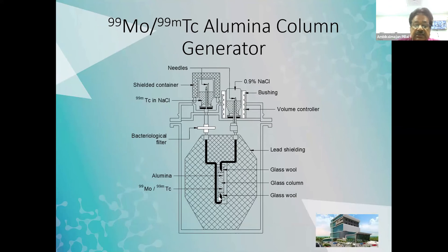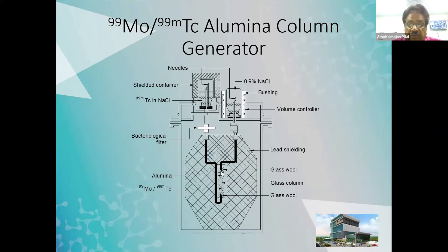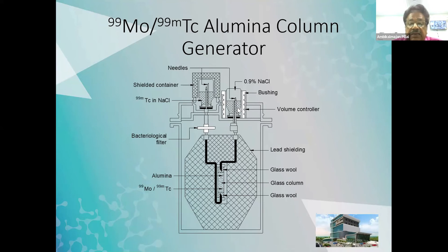The generator is kept in a lead shield so that when we are handling and using it, the radiation dose is minimum. This is the column with molybdenum adsorbed in it. We keep a 10 ml saline vial at the top, and on the other end we keep an evacuated vial. The saline is drawn through the tubes, comes to the column, elutes the pertechnetate, passes through a filter, and comes out into this vial, which is now ready to be used as a radiopharmaceutical.